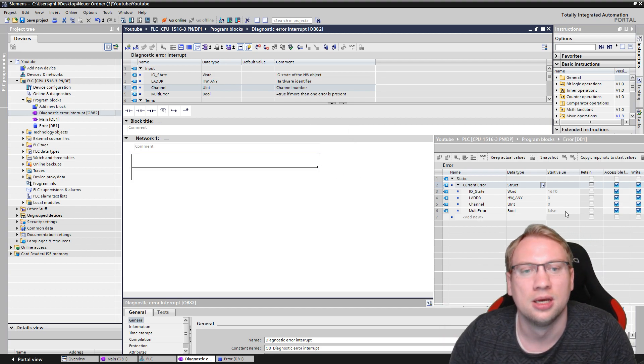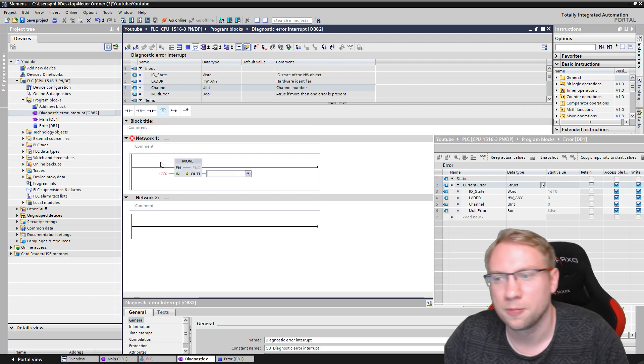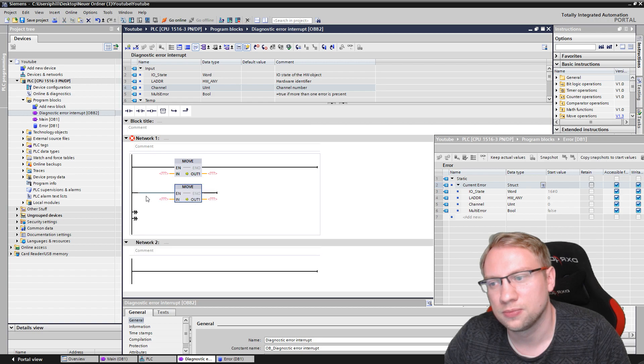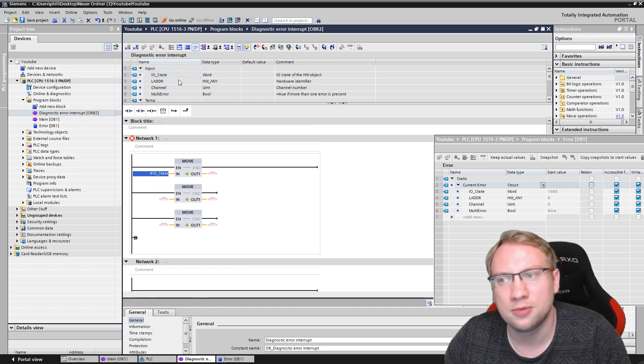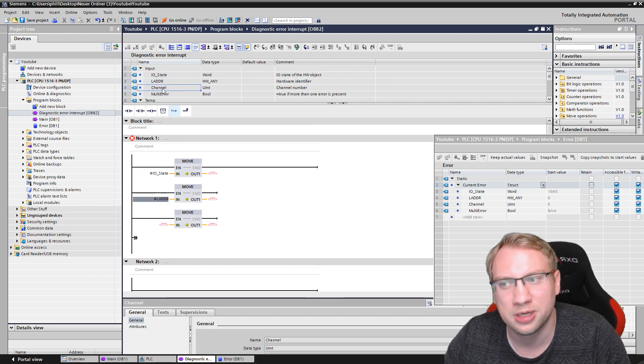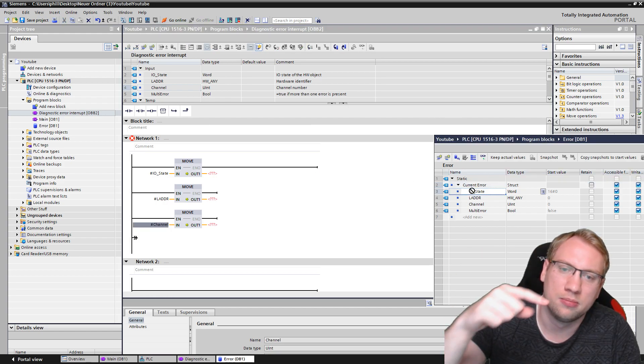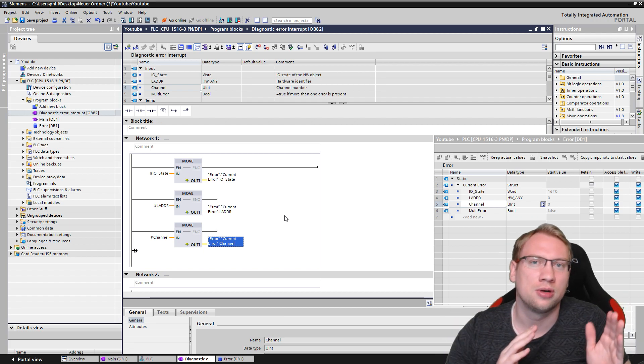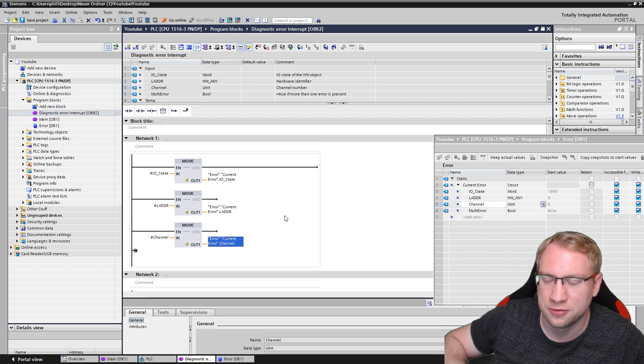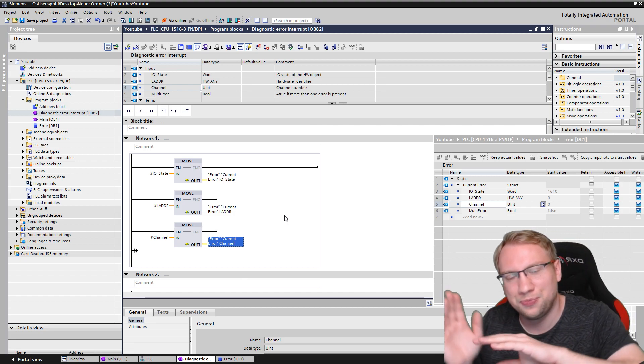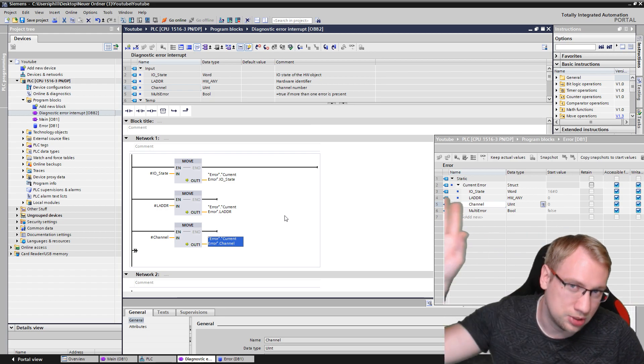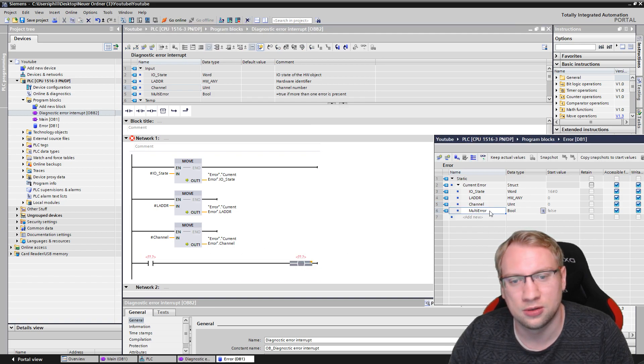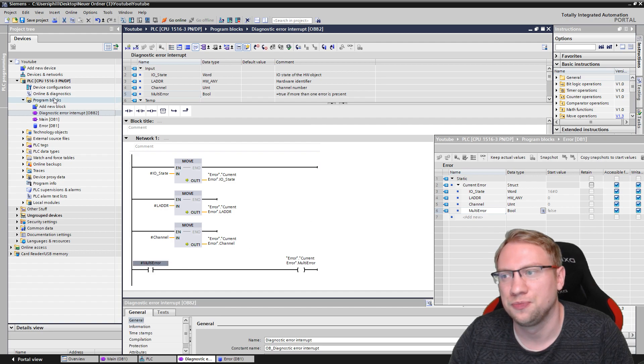Whenever OB82 is executed, I want to push those four variables into my data block. I'll use MOVE instructions for the first three — io_state, laddr, and channel — because they are word, hardware identifier, and unsigned integer types. I move them from OB82 into my data block. As a user I can now display these on an HMI or use them in my program to react — for example: if module 257 has an error, turn off all motors but keep hydraulics on. And I'll also push multi_error.